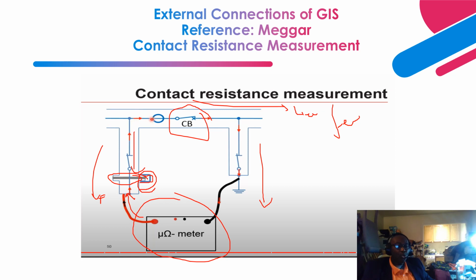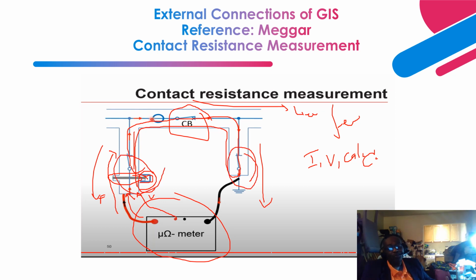So you inject your required current, and it flows through this part. Then you have another lead that measures the return voltage. You have an injected current, you have a measured voltage, then you can determine your contact resistance. But one caveat is that the contact resistance includes the resistance of these switches. So what you can do is find out the factory testing results for these disconnect switches, and determine the parallel resistance of these disconnect switches and the circuit breaker to find the actual circuit breaker resistance.